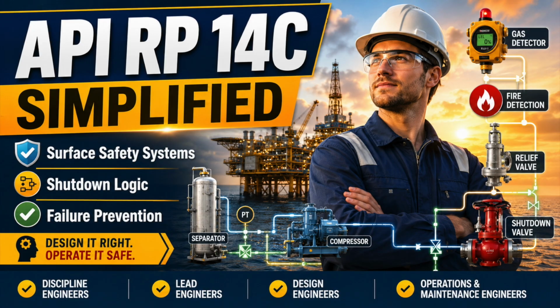A small liquid leak may be masked by level control replacing the lost inventory. Low-pressure trips detect large leaks. Gas detectors detect accumulation. Containment systems collect liquids. Fire detection responds after ignition. Human observation detects conditions no single instrument was designed to interpret. Each layer has a defined detection envelope. Do not pretend that one instrument covers every leak size.